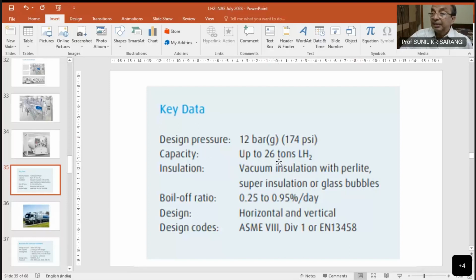It's then further evacuated, but at a low quality evacuation, something better than 100 micron pressure, so like a microbar pressure. So we are not talking of plain perlite insulation. Large oxygen plants are actually insulated using perlite powder at atmospheric pressure, but this insulation is evacuated perlite, which is good quality. But better than this is called super insulation.